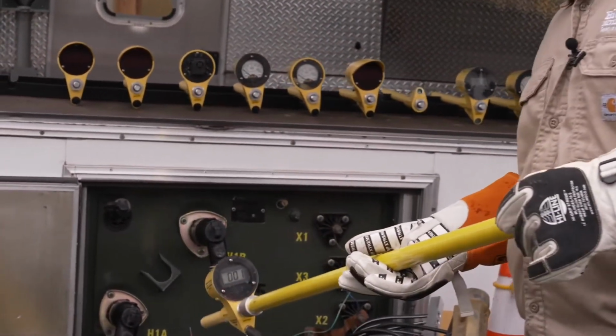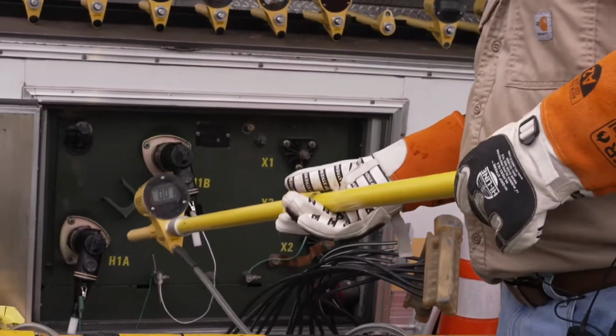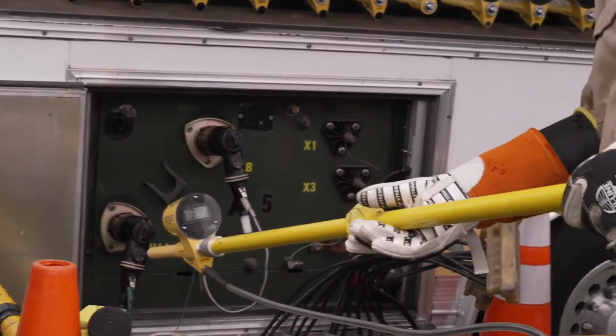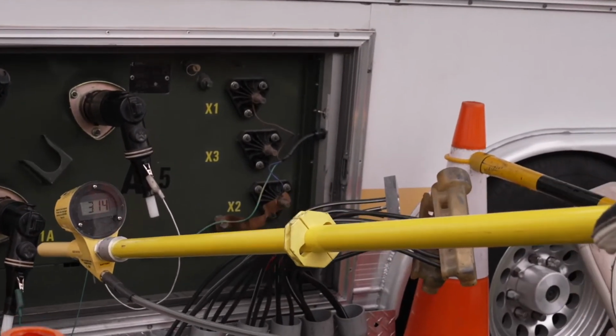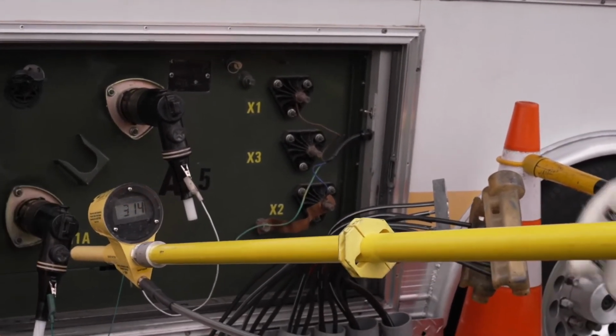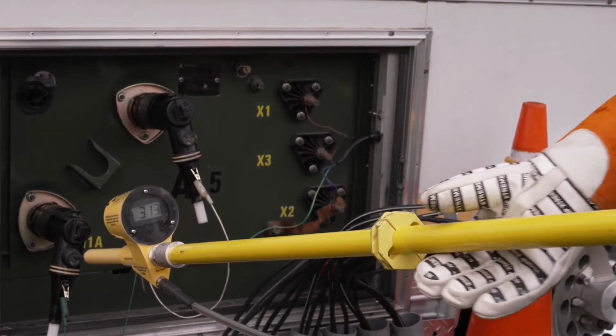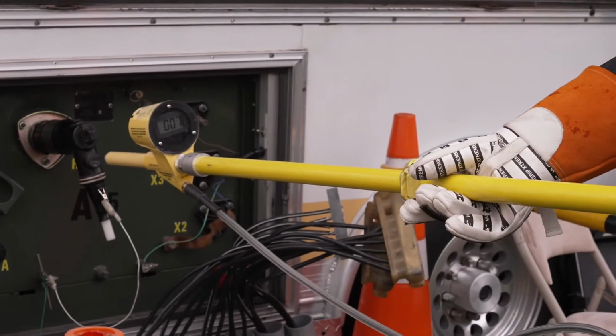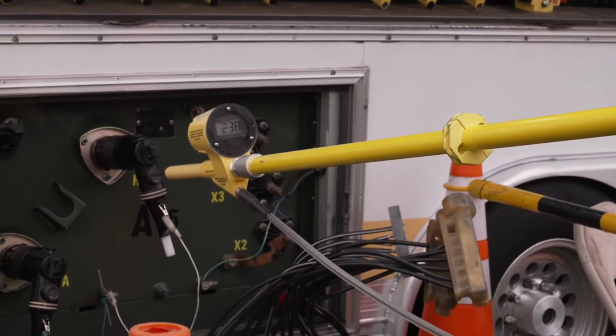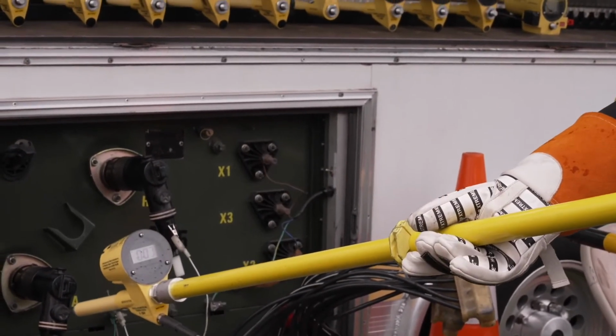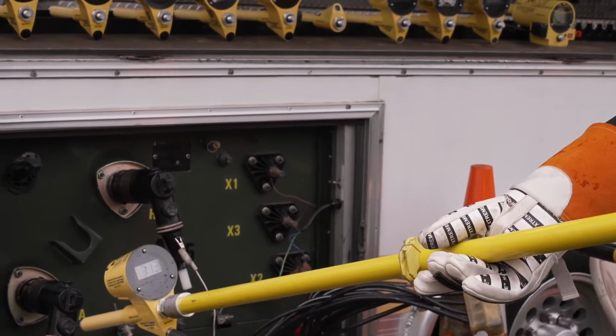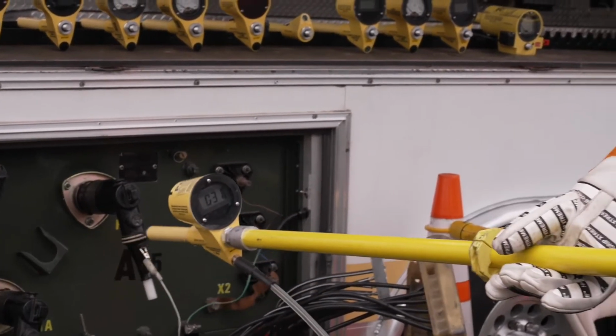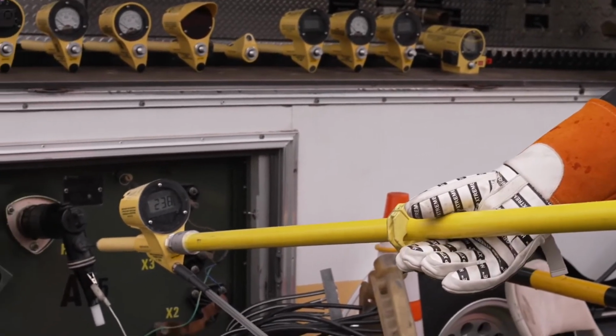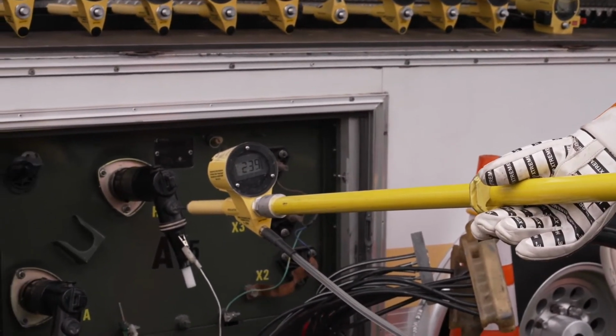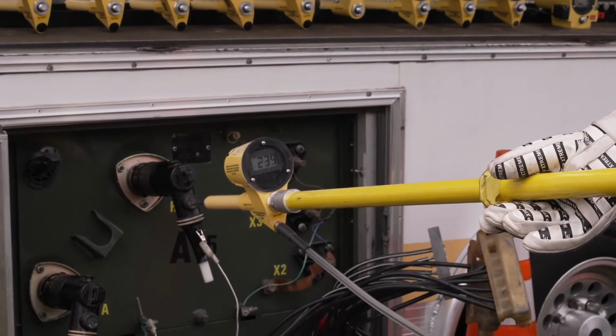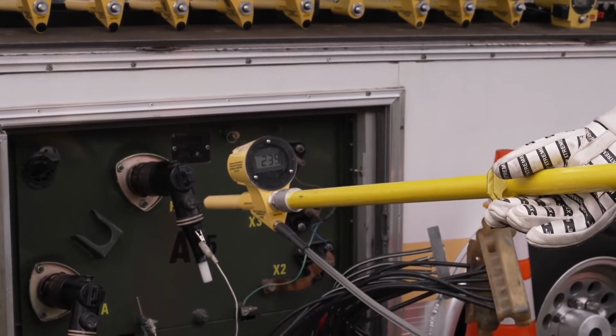So you take the phase to ground reading on the first elbow, and you see about 314 volts. You want to remember that number, because if you go to the next elbow, phase to ground, and you see 230 volts, what was the difference there? About 75? Yeah. So you remember the two voltages, and if you're in phase, you're expecting to see the difference of those two voltages, so about 75, 80 volts.